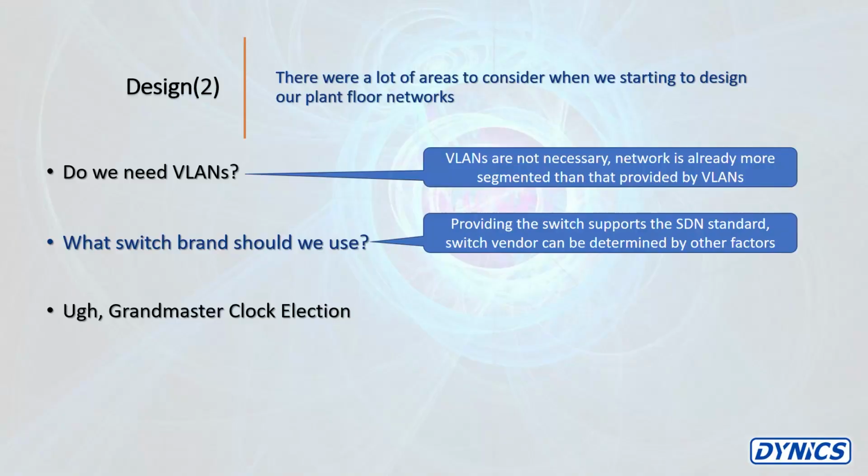If the Grandmaster clock was the little bitty PLC 27 hops away, on a non-1588 switch, any more than 7 hops and the disparity in time syncing becomes too great, you were toast. So all of a sudden, what we found out was, hey, we actually have to care about where this Grandmaster clock is, because when we're doing motion, it's critical, right?